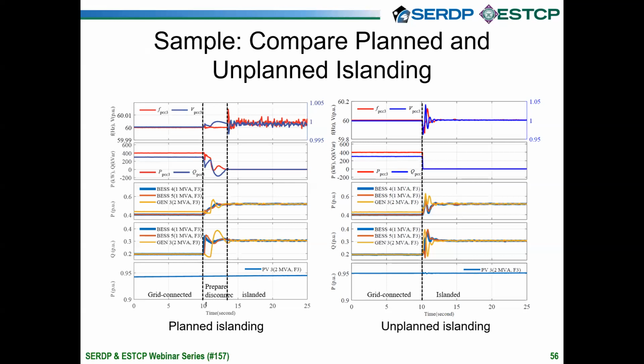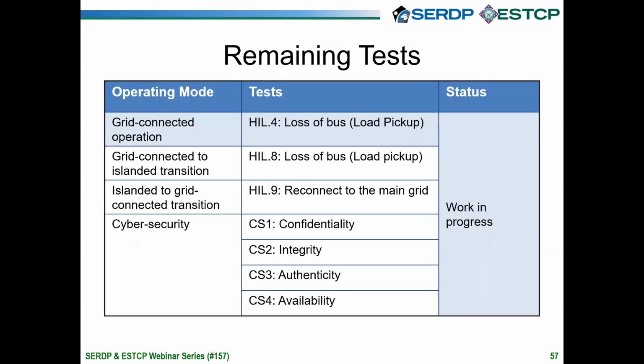On the right side, this is the abrupt disconnect, and we are able to handle that as well. So the project still has a number of remaining tests that we want to perform. One of them is what happens if we are in grid-connected operation and we lose a bus. In this case, we have to rapidly adjust the distributed controller to pick up the loads. And the other two tests, for which we actually have most of the work done, are the transition tests. So grid connected to islanded, together with a loss of bus, as well as the islanded to grid connected transition, where we are reconnecting to the main grid.